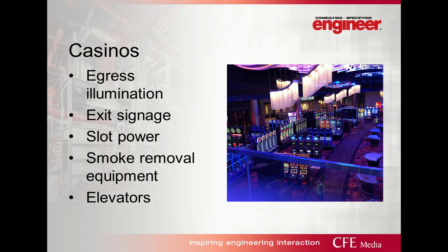Exit signage is another item that has to be put on emergency lighting. In this photo here, you really don't see any exit signage, do you? It has to be within 100 feet of where you're standing in all cases. There is one, it's just this picture didn't show it. Slot power. Slot power is not an emergency power system or a 701 system, legally required. It is optional standby, which is Article 702 in the NEC.